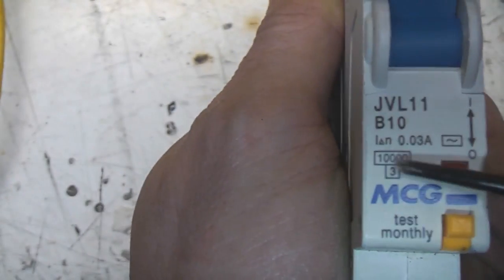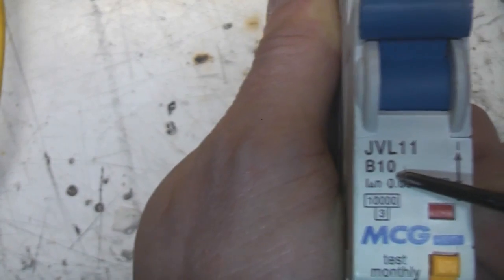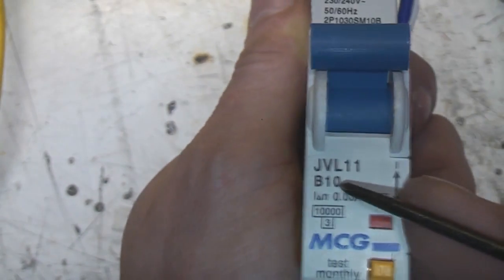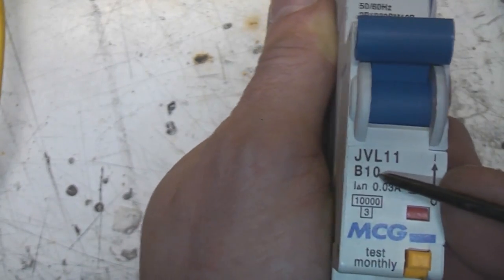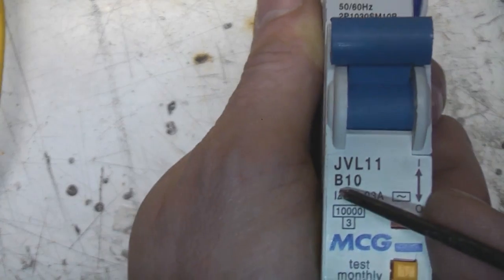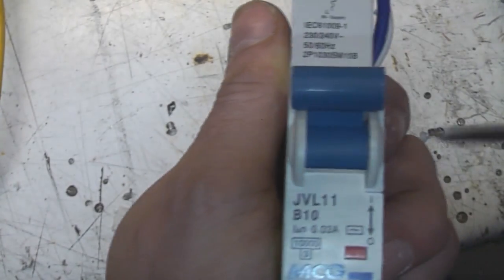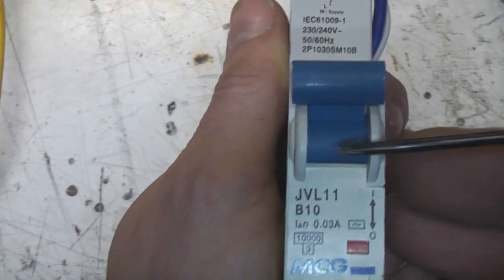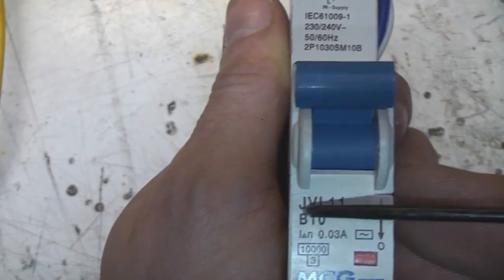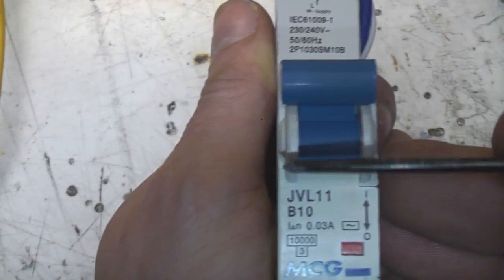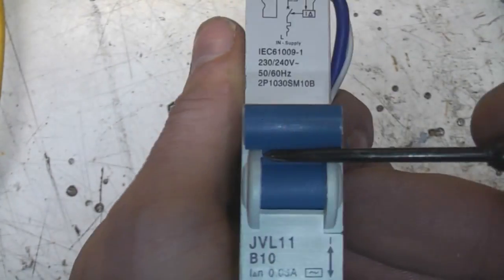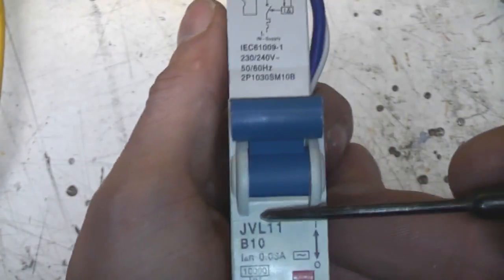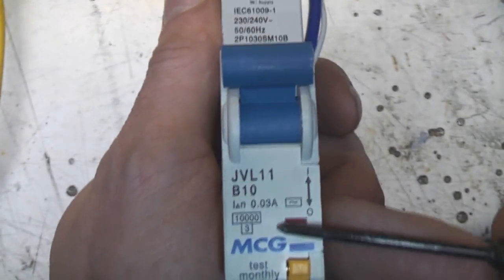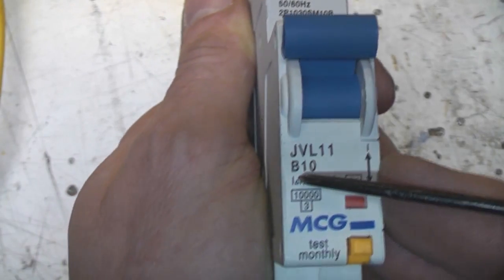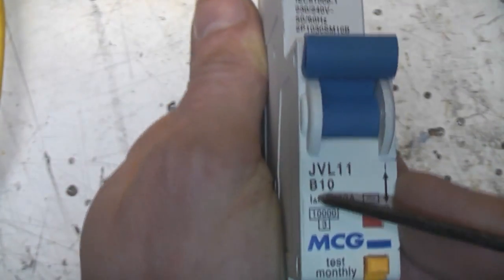There's a few other numbers here. So B10, that's the actual overcurrent category. 10 is the current rating, so it's designed for circuits that run 10 amps normally as the maximum working load. B is the time characteristic. These have two aspects: a thermal trip and a magnetic trip. The thermal trip is designed to operate on relatively small overloads over a long period of time, whereas the magnetic is designed to react to high currents very quickly, to prevent arcs and wires exploding and so on. And the B is the time characteristic of the magnetic part of it.